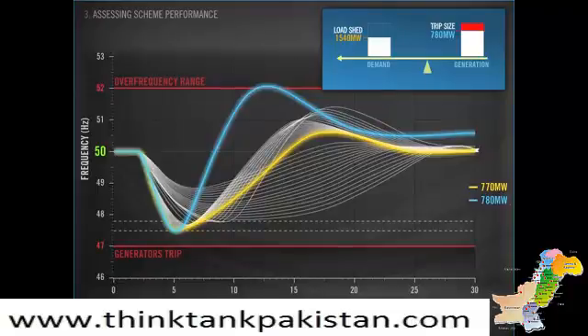In terms of scheme performance, that's what we call non-performance. The scheme was unable to prevent the frequency from rising above 52 Hz, which could result in loss of additional generation and system blackout. This is clearly a situation we want to avoid. As the size of generation loss increases, the amount of overshed decreases, and the frequency stays within the desired range.